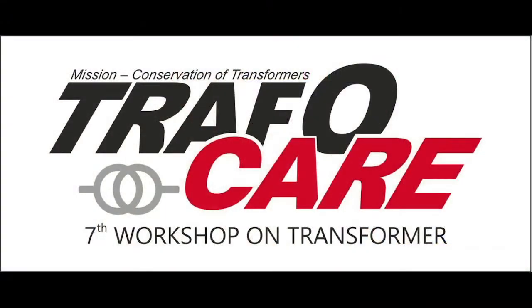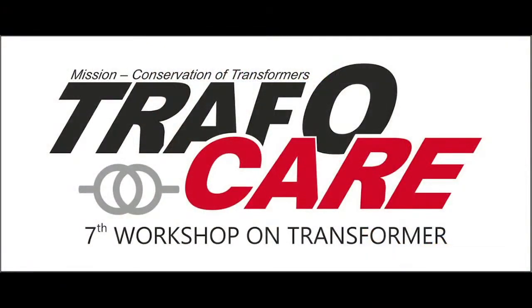So I hope that answers the question. As far as possible, we should avoid dual ratio transformers; if that's not possible and flexibility is needed, please go for it, because these transformers have existed for ages - for example, 33 by 11 kV and 33 by 22 kV transformers have been used for a long time. So these transformers do exist, but if you want more confidence, please go for short circuit testing of those transformers, which will definitely improve their short circuit reliability.